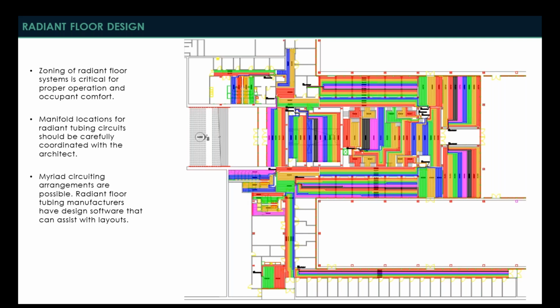And it's also important when you're talking about zoning because it goes back to the idea of the manifolds that you're using for these radiant floor systems. And their locations can be very critical. Wouldn't be the first time that I laid out a radiant system and thought that I had a real good idea of where I wanted my manifold to go, only to find out later that that's an architectural feature wall and they don't want to see an access panel, etc. So it's very important for the design team to work together to figure out the locations for these. And then there are so many different possibilities when you talk about the circuiting arrangements. Working directly with the radiant tubing manufacturers is a great way to utilize their proprietary software that can assist the designer in laying out some of these spaces.